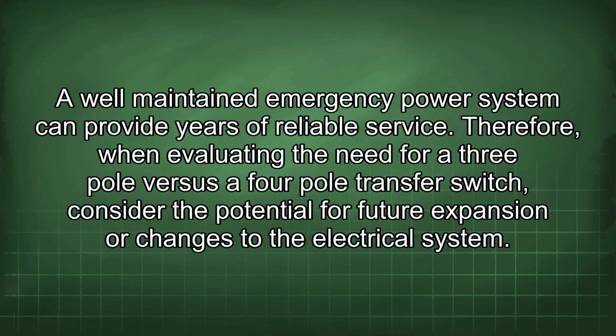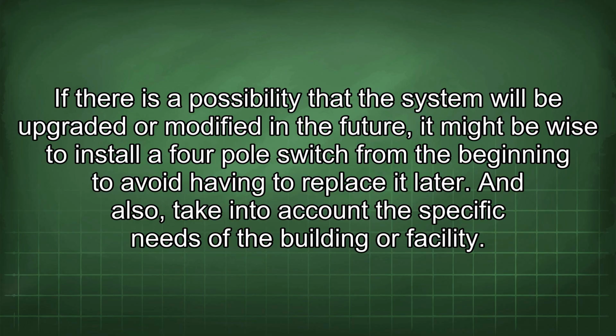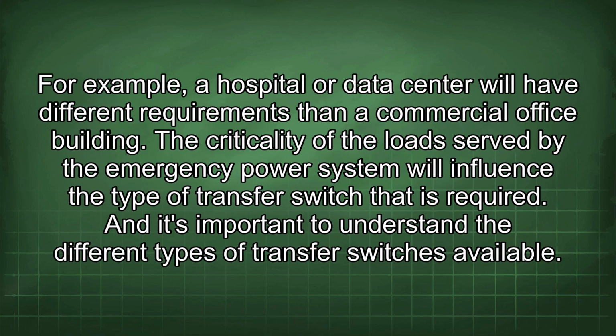Therefore, when evaluating the need for a 3-pole versus a 4-pole transfer switch, consider the potential for future expansion or changes to the electrical system. If there is a possibility that the system will be upgraded or modified in the future, it might be wise to install a 4-pole switch from the beginning to avoid having to replace it later. And also, take into account the specific needs of the building or facility. For example, a hospital or data center will have different requirements than a commercial office building. The criticality of the loads served by the emergency power system will influence the type of transfer switch that is required.